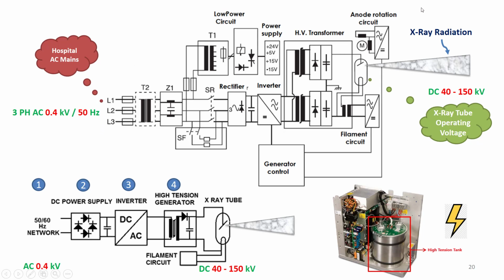In this slide, we see a block diagram of a high-frequency X-ray generator which is connected to an X-ray tube. The X-ray tube of a DRF system requires a DC voltage with a range between 40 up to 150 kilovolt, whereas the hospital power source is a UPS system, or uninterrupted power supply system, which provides us with a 400 volt 3-phase waveform. So we need to make a match between the voltage of the hospital source and the requirements for the X-ray tube. In the past, we used a high voltage step-up transformer with a variable magnification power between 100 and up to 375 times. Then we rectify the output of this high voltage step-up transformer and supply it to the X-ray tube. The problem with this high voltage transformer is its size. It's so bulky.